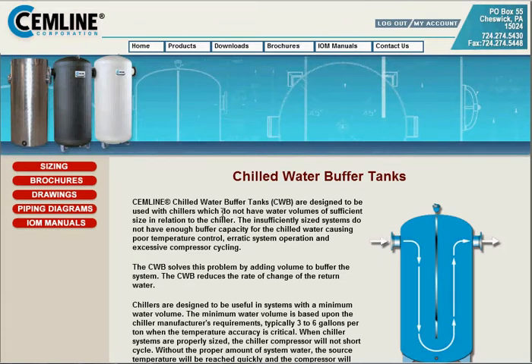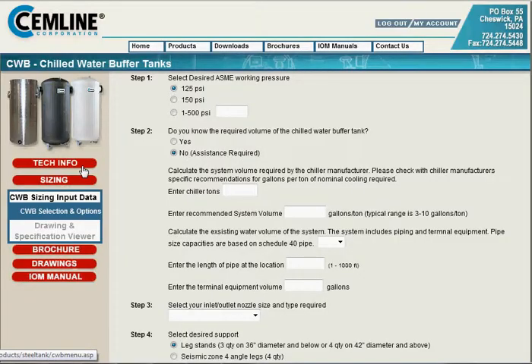Cemline chilled water buffer tanks are designed to be used with chillers which do not have water volumes of sufficient size in relation to the chiller. Insufficiently sized systems do not have enough buffer capacity for the chilled water, causing poor temperature control, erratic system operation, and excessive compressor cycling. The CWB solves this problem by adding volume to buffer the system, and reduces the rate of change of the return water. To begin sizing, we click the sizing button.